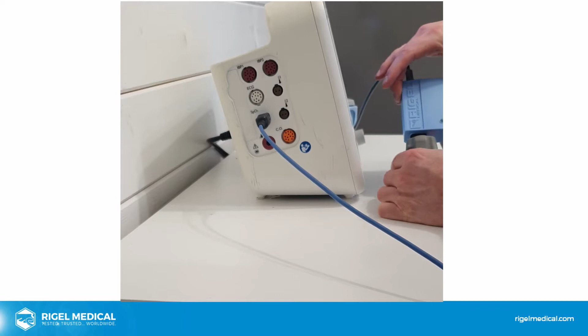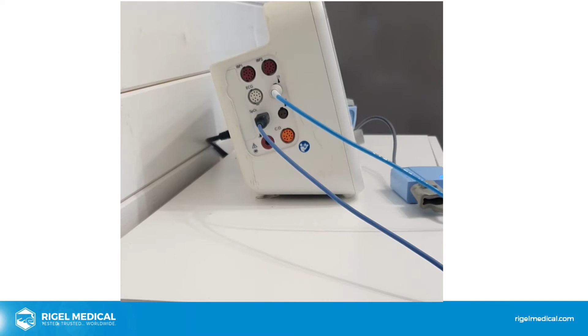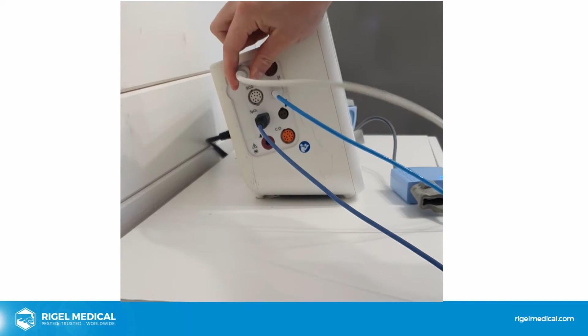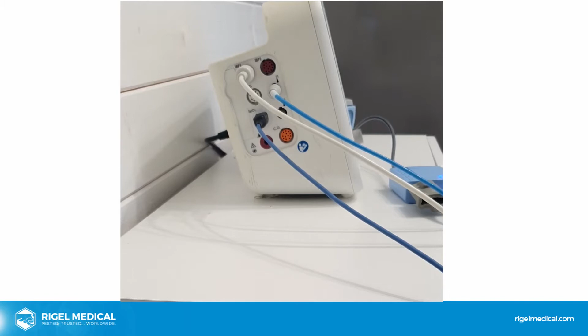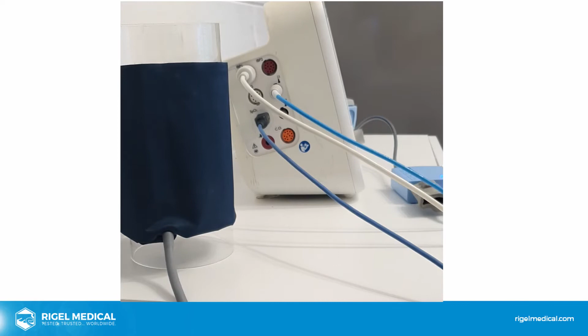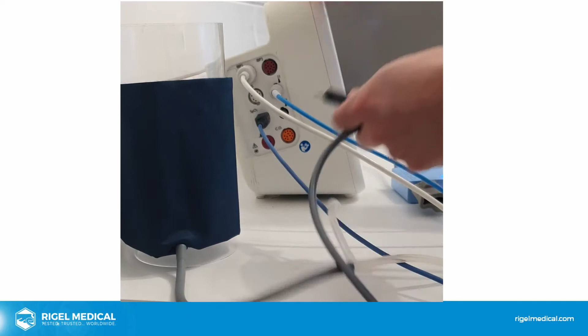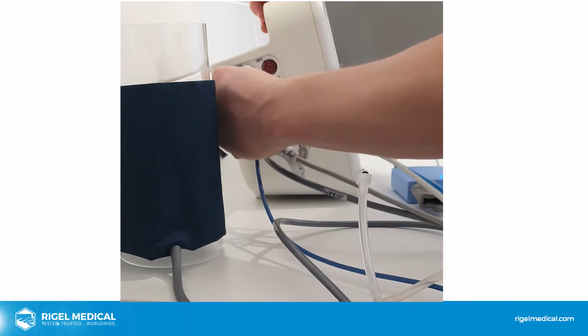And then from the Uni-Sim we want to connect our temperature cable. So we're going to go to temperature port 1. We've got IBP 1. And then for NIBP, you need to use some sort of cylindrical piece of equipment for the cuff. We've actually got a piece of cylindrical plastic perspex, and then from here, this is where we want the NIBP to connect to the back of the Uni-Sim, or NIBP connection. So we've got a T-piece. This goes to the Uni-Sim, and this plugs into the patient monitor here. And then we've got our ECG connections that plug in here.